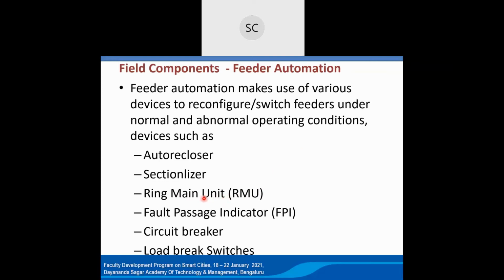So when a fault happens, we can quickly isolate remotely when it is automated. The lineman will not have to go to the physical place where the ring main unit is located. We can quickly disconnect or connect remotely. We can limit the fault to that area alone, isolate it from the rest, and power can be restored to the rest of the area through an alternate path. It can be two feeders from the same substation, or from different substations, so it provides alternate paths. That is the advantage.